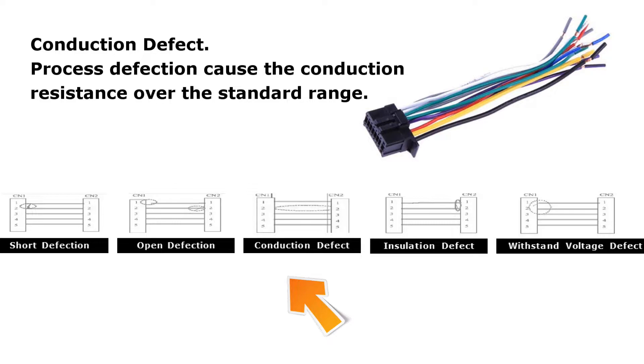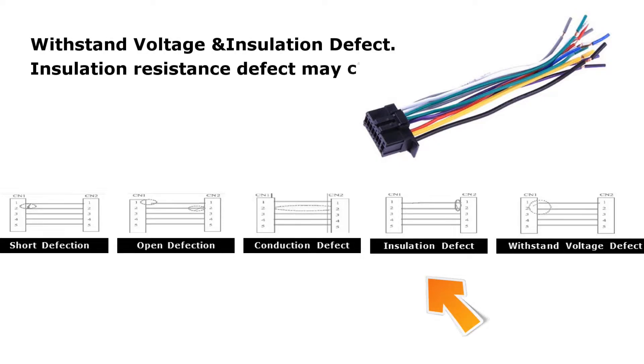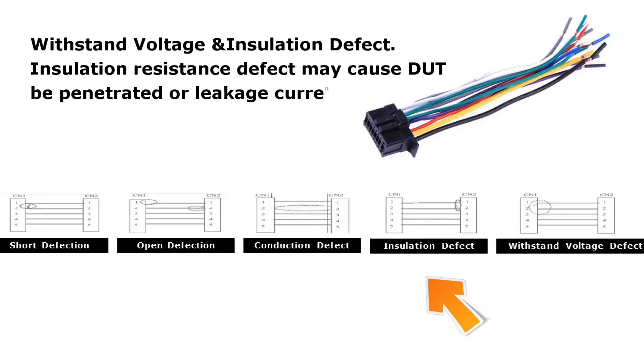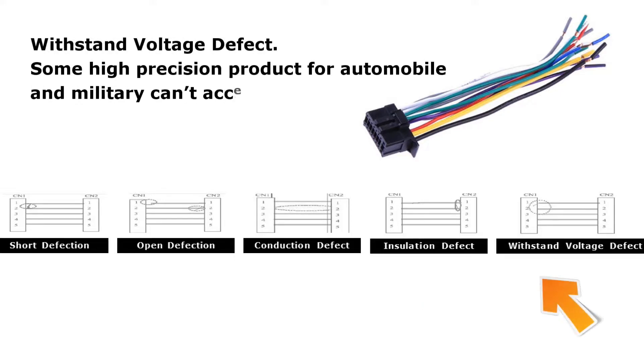Process defects can cause conduction resistance to exceed the standard range. Withstand voltage and insulation defects — such as insulation resistance defects — may cause the DUT to be penetrated or cause leakage current under high voltage. Some high-precision products for automotive and military applications cannot accept any arc under high voltage.